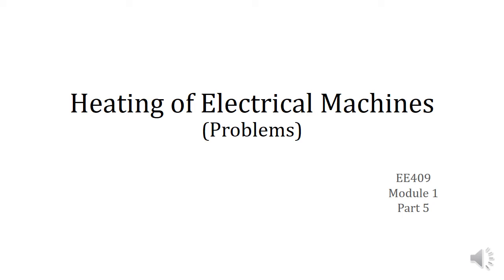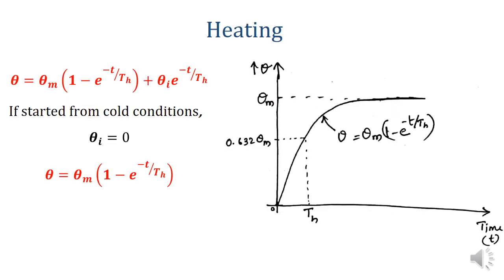Today we will practice some problems on heating of electrical machines. The equation for a machine under heating is given by theta equals theta_m times (1 minus e raised to minus t by th) plus theta_i times e raised to minus t by th, where theta is the temperature rise, theta_m is the final steady state temperature rise, and theta_i is the initial temperature rise. If the machine is started from cold conditions, theta_i equals 0, so the general heating equation becomes theta equals theta_m times (1 minus e raised to minus t by th).